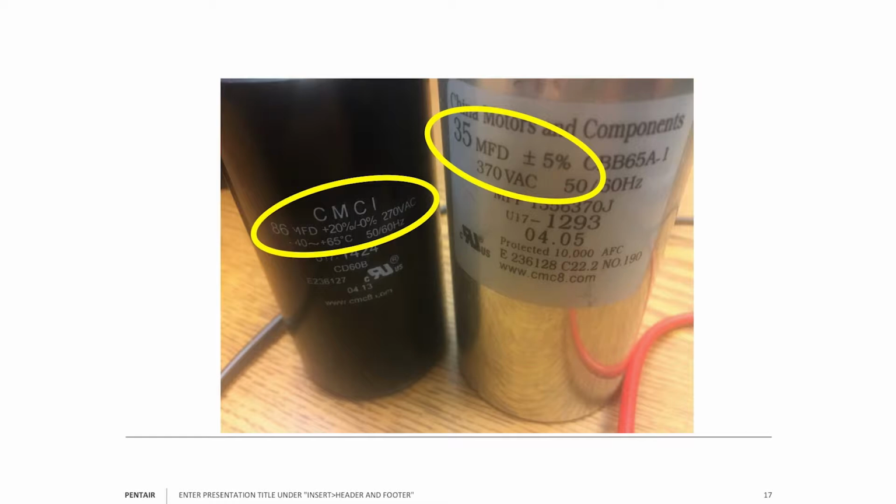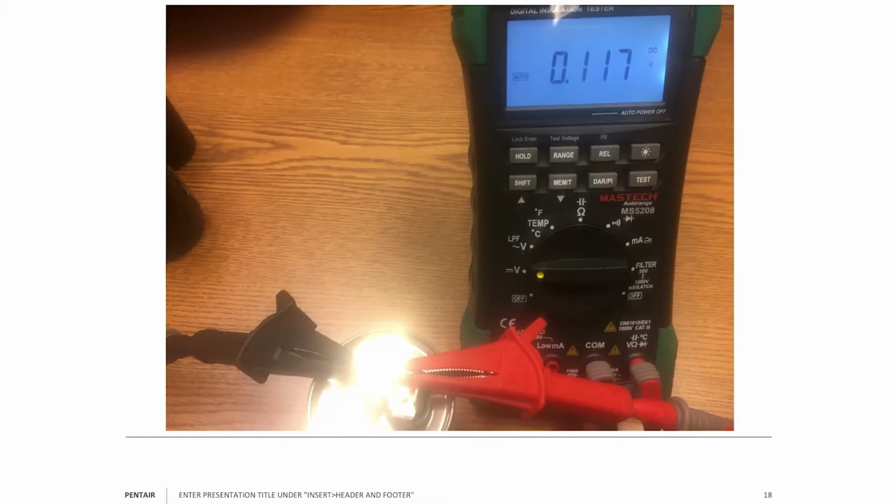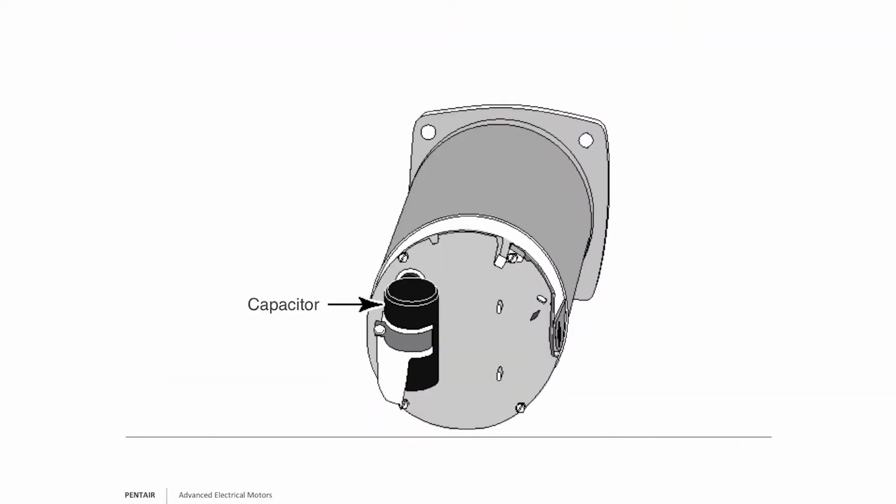By upping the voltage, again, you improve your insulation class is what you're doing. Now, I mentioned how you can discharge a capacitor: with an insulated screwdriver, run the blade of the screwdriver across the points. It should discharge it. When in doubt, hook up your voltmeter to DC and measure across the points. You should measure less than half a volt, knowing then it's safe to handle.